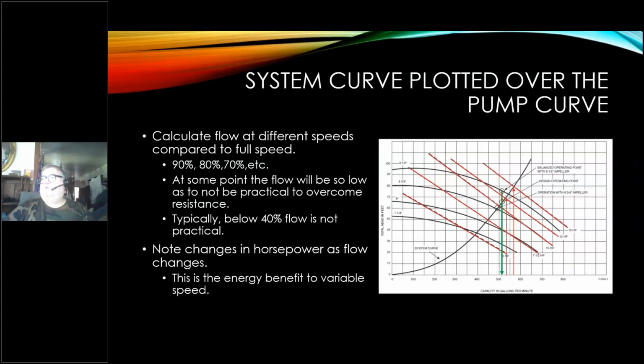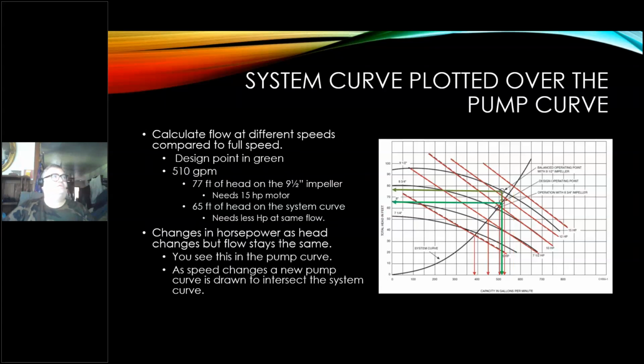But we get the benefits of variable speed by reducing the flow and different points along the system curve all the way down. So in this case, we calculate the flows at different speeds compared to full speed. Remember also, here our design point is in green. Every time you change the speed, you're not changing the size of your impeller. You're just redrawing this curve for that impeller every time you change the speed. There are actually software packages that can do this for you. I believe Bell & Gossett may have one, but you may have to pay for it. Once you plot the curve for full speed and then punch in the change in speed, it recalculates the curve and gives you better numbers for your actual horsepower, head, and flow. Then you have an idea of what your real numbers are versus calculating them using the affinity law.